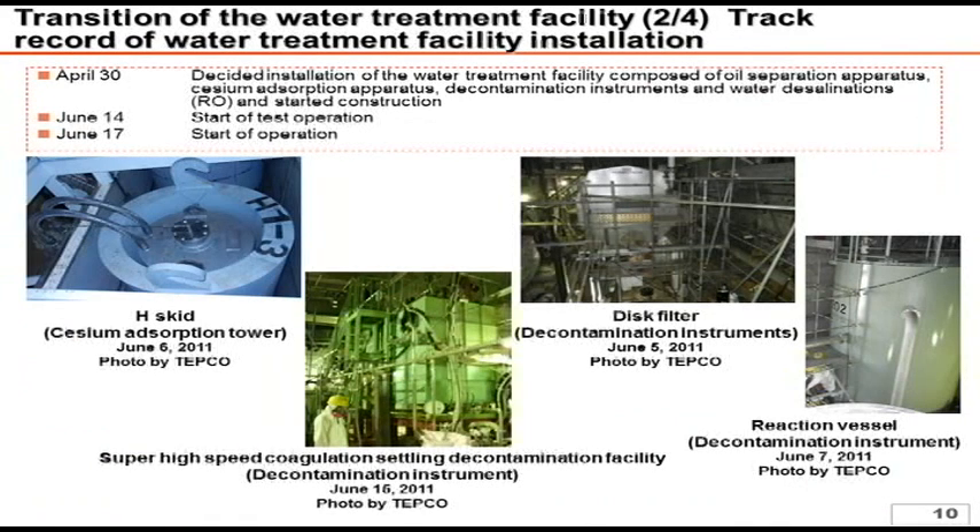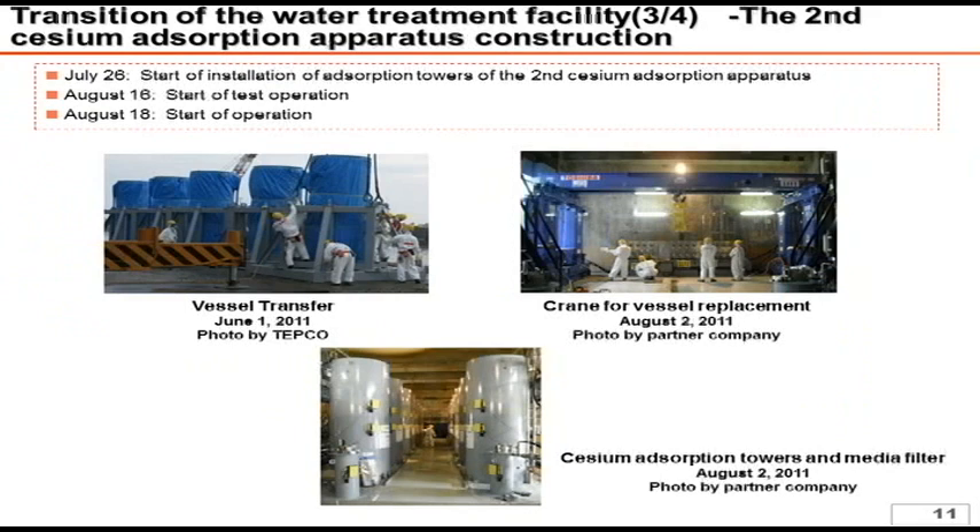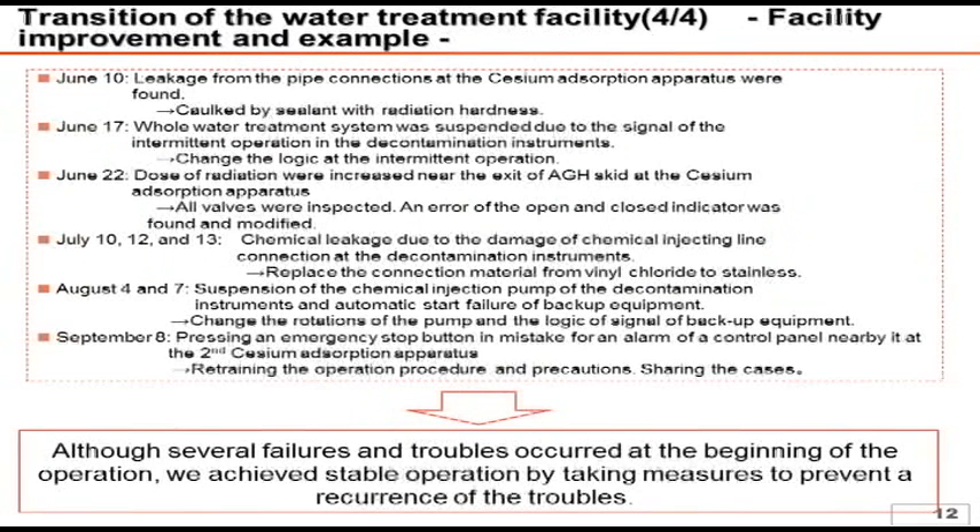On April 30th, we made a final decision regarding the water treatment system including water desalination, and the construction has been in progress. We started trial operations from June 14th and started official operations from June 17th. Regarding Toshiba's SARRY, as it took a little time for designing and manufacturing, the installation work started from July 26th and trial operations started from August 16th, with official operations starting from August 18th. While we started operation of the water treatment system from June, a variety of troubles has occurred. The major troubles are listed in the handouts. In Curion, there was leaking at the connection of the piping and the rupture disk. In Areva, the whole water treatment system was shut down due to the signal of intermittent operations. Also, chemical leakage at the chemical injecting line happened several times. We now believe that we have overcome these troubles and have achieved stable operations.